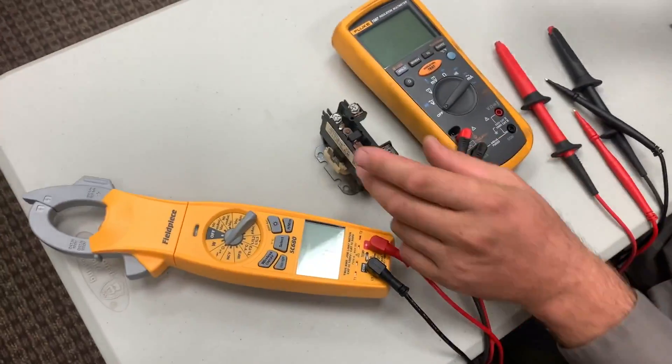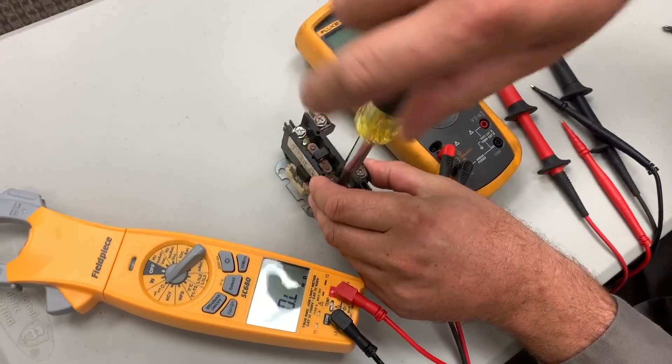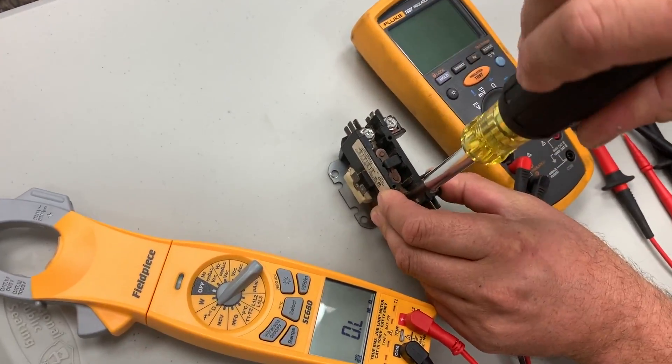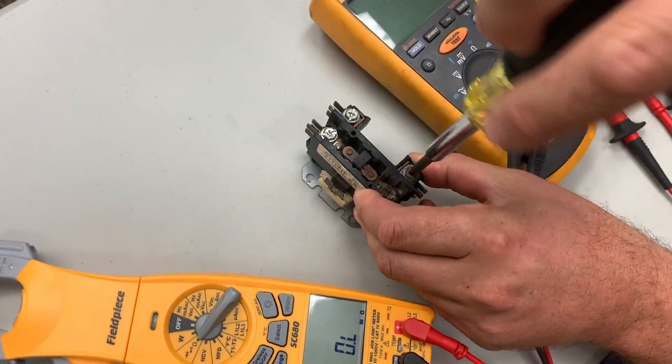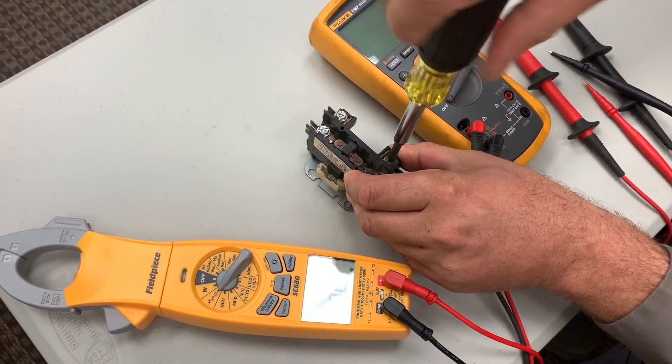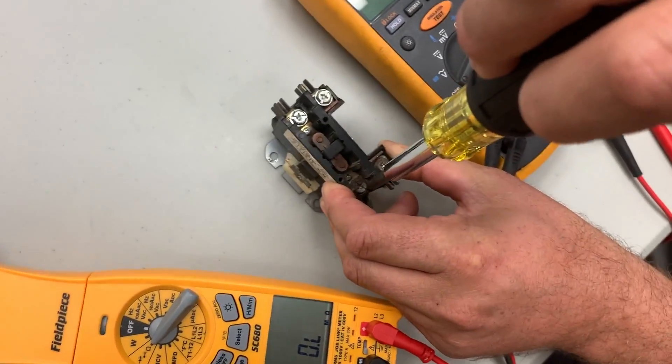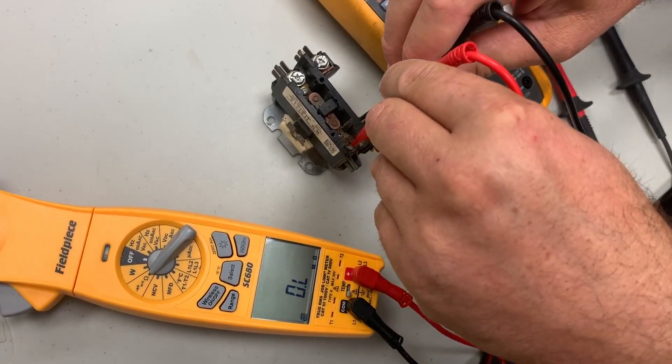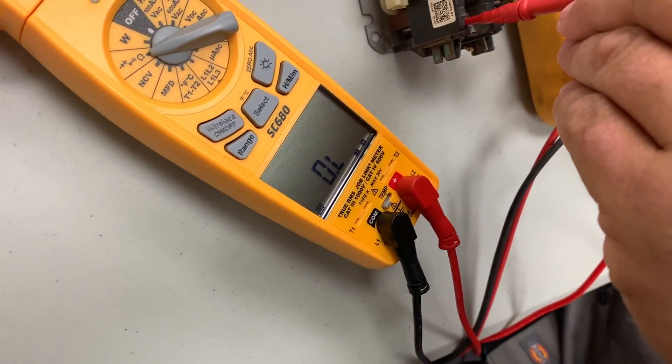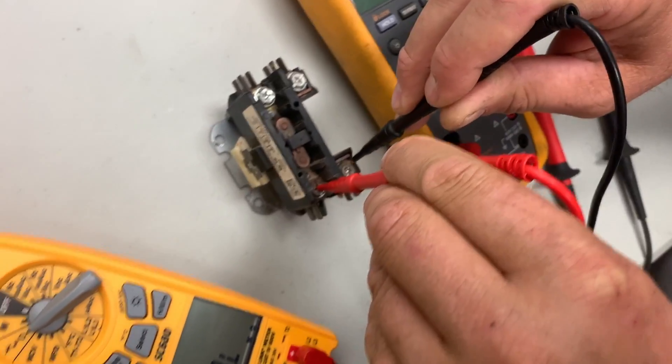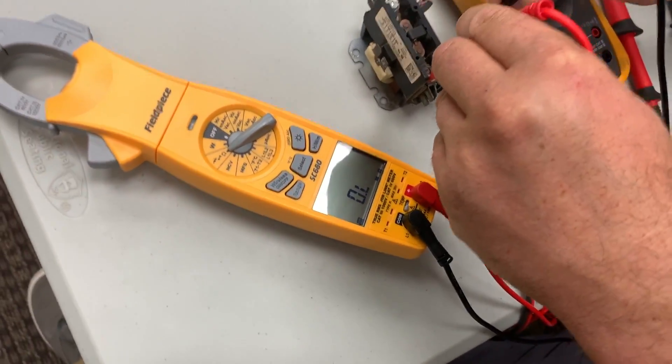But then we tighten the screws down like they would be when the system was in operation. Remember, this was an intermittent problem. We'd show up, breaker's tripped, we'd reset it, and we really couldn't figure out what was going on. Still not showing anything. Previously when we tightened it down we actually did, but we're not now.